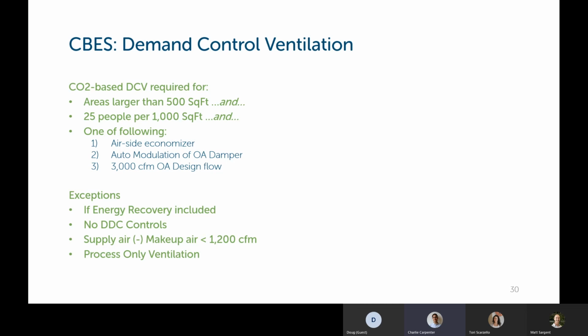If you've got an energy recovery ventilation system in that space, then you're not required by code to also do demand control ventilation. That is something that you can put in for additional energy savings if needed. If there's no direct digital controls system for that space, you do not need to do demand control ventilation. It'd be hard to control that way. If the supply air less the makeup air is less than 1,200 CFM, then it's a small enough system that you don't need demand control ventilation. And if the ventilation is just for process applications, not occupants, then you do not need demand control ventilation.